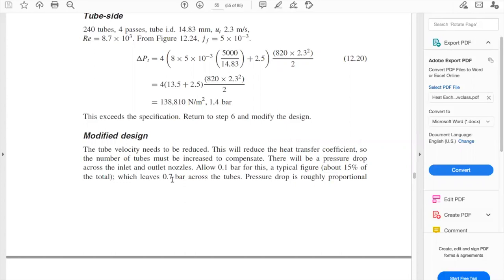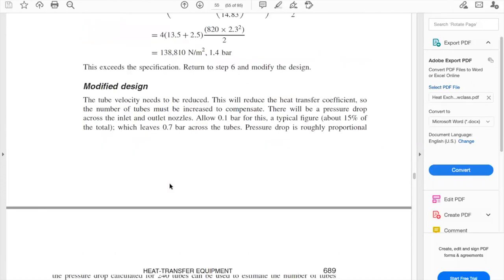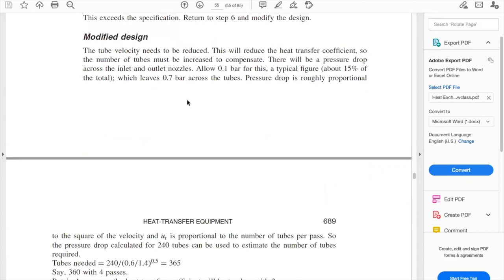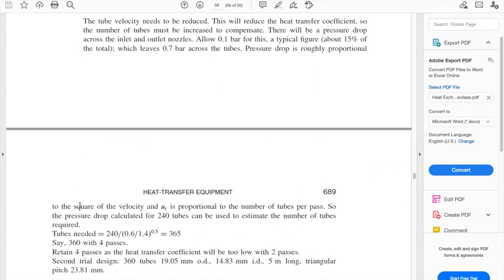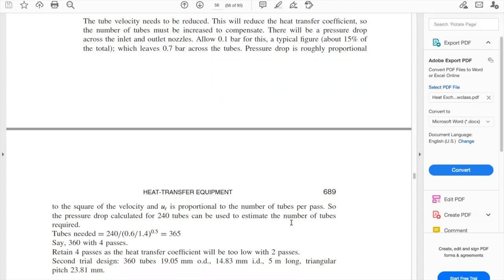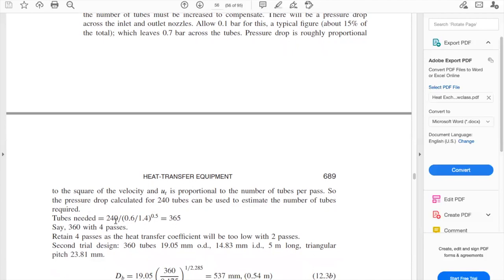This is an approximation, so you as a designer are free to say you want to consider 0.6 or 0.8 bars — it depends on whether you want to over-design or stay just below the permissible value. These informed decisions get better with more practice. Pressure drop is roughly proportional to the square of the velocity, and the velocity in the tubes is proportional to the number of tubes per pass. So the pressure drop calculated for 240 tubes can be used to estimate the number of tubes required.